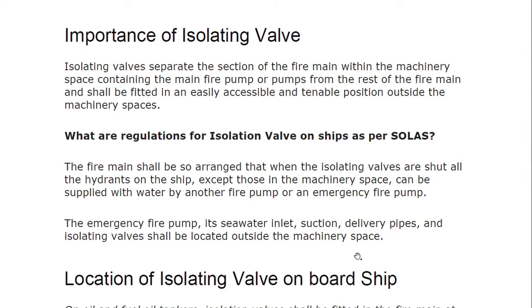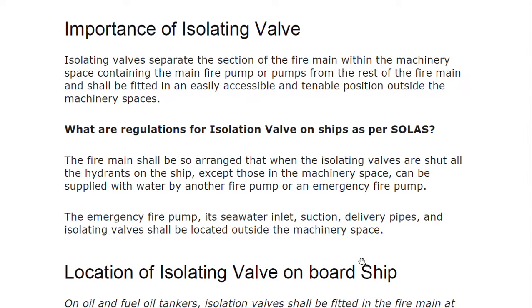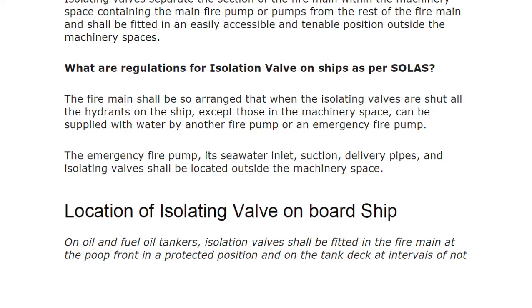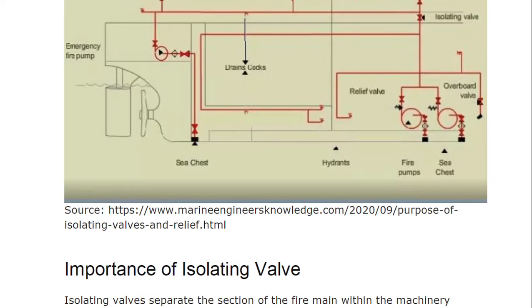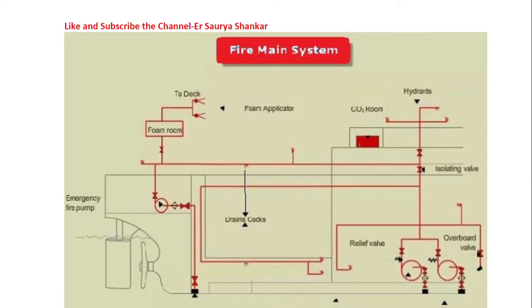Regarding location of the isolating valve on board: on oil and fuel oil tankers, an isolation valve shall be fitted in the fire main at the poop front in a protected position, and on the tank deck at intervals of not more than 40 metres, to preserve the integrity of the fire main system in case of fire or explosion.